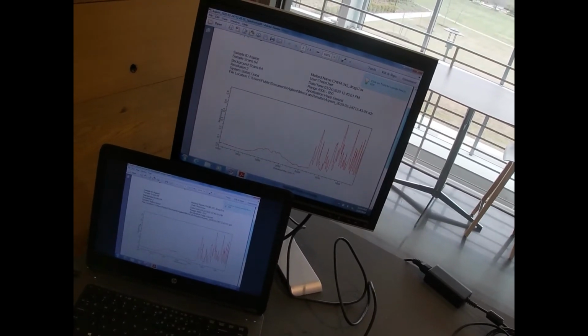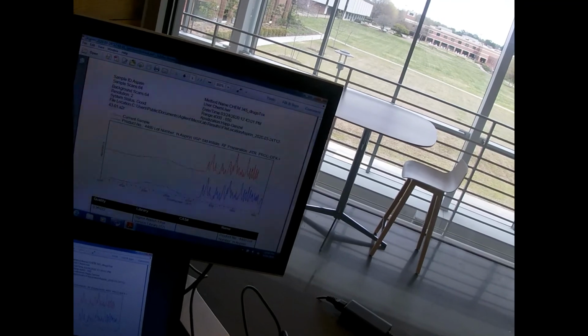We have sample ID, it's aspirin. All right, so I just wanted to show you, this is where we actually got our match. This is a USP aspirin sample compared to our current sample. And so here's where we actually get our match. We have 0.9622, which is about 96% match. So we did identify it as aspirin. That's awesome.